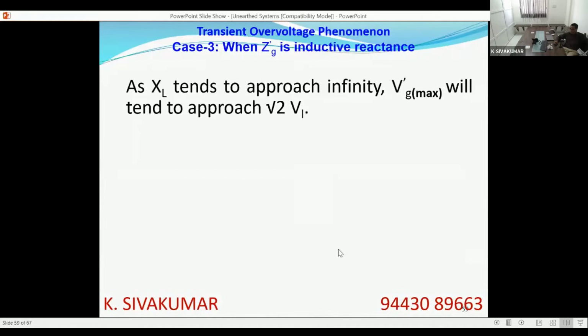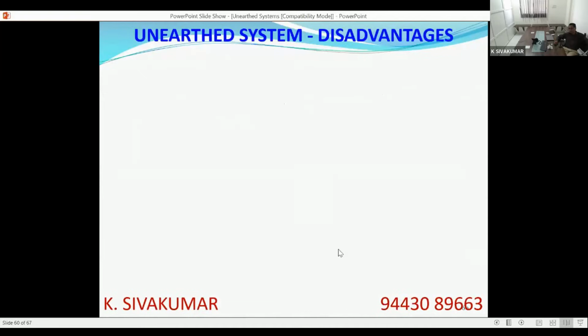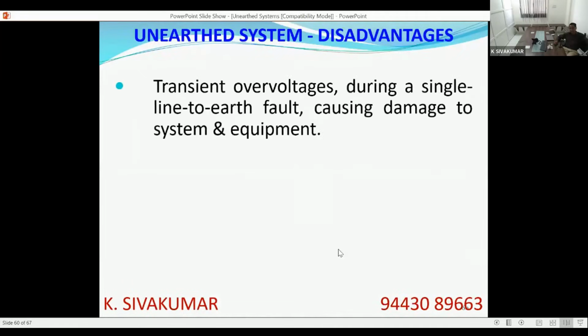So the danger here is that whenever the system network inductive reactance is equal to the capacitive reactance during an earth fault, there will be very high overvoltage thrust on the system, which is not good. Summing up the disadvantages of the unearthed network, as we have seen in the previous slides, there will be huge transient overvoltages during a single line to ground fault, causing damage to system and equipment. We cannot design our system to tolerate this high voltage because it will make our system and equipment costly, so we generally economize in our design. We design our system for tolerating nominal overvoltages, so in an unearthed system, when this happens, system and equipment get damaged.